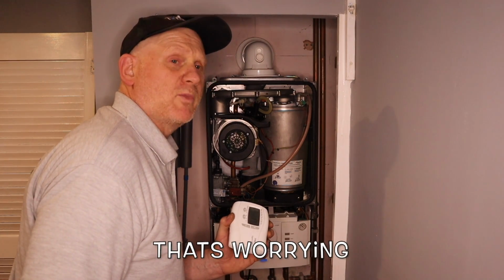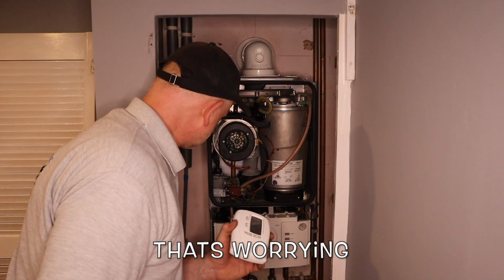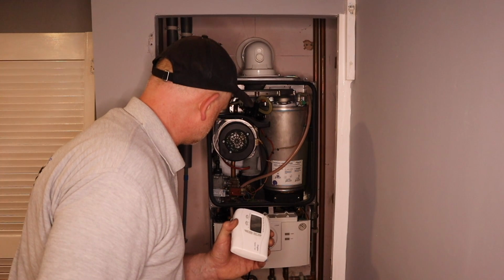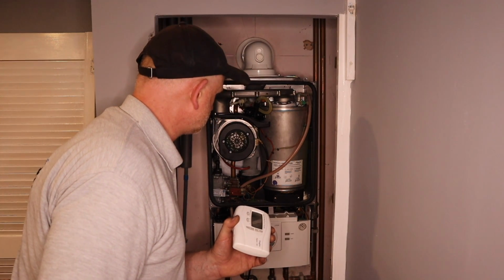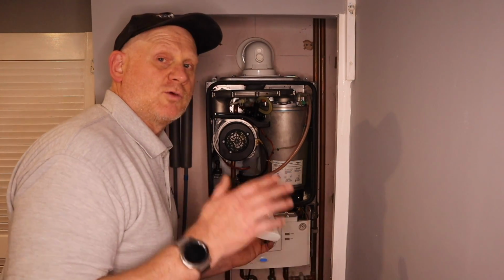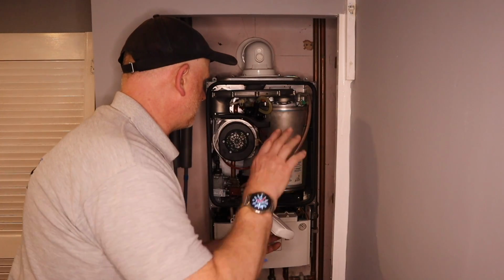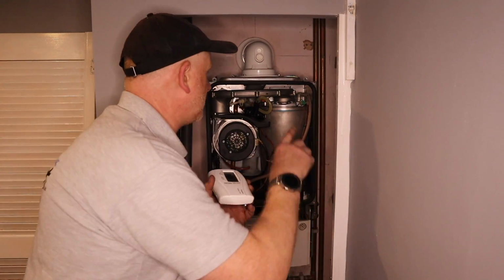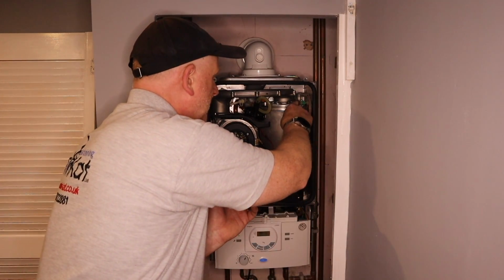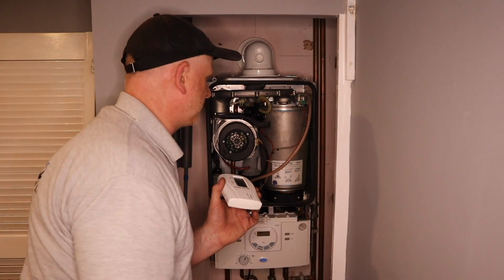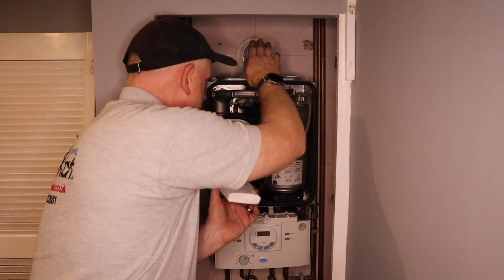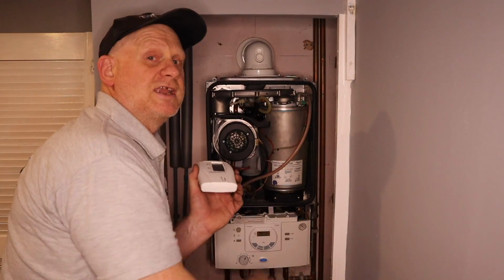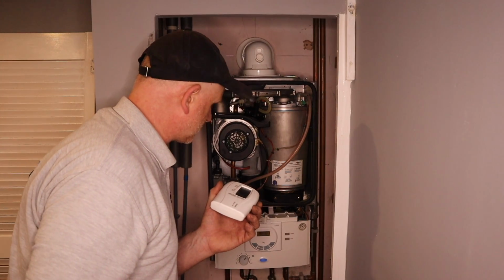Oh, there's a little pop when it fired up. So what I need to do now is leave it running for a few minutes, and then I need to test around here. We're doing a sweep test to see if the gasket's okay. I need to flue gas analyse it, and I need to do my inlet pressures.